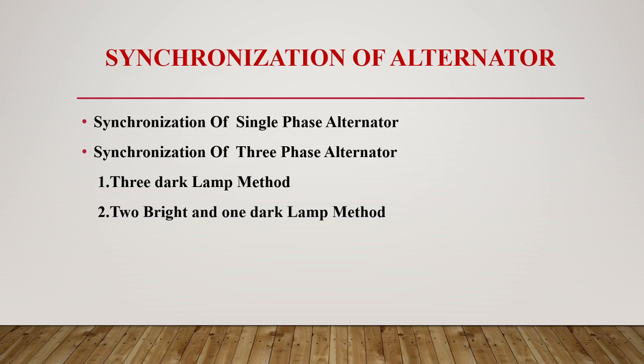The process of connecting an alternator in parallel with another alternator or with a common bus bar is called synchronization. We can connect two alternators in parallel, or connect an alternator with a common bus bar. So what is the bus bar? The bus bar is the one to which a number of alternators are already connected. So, conditions for proper synchronization.